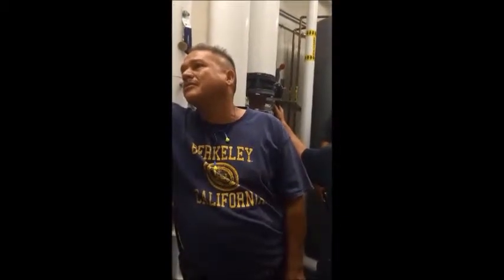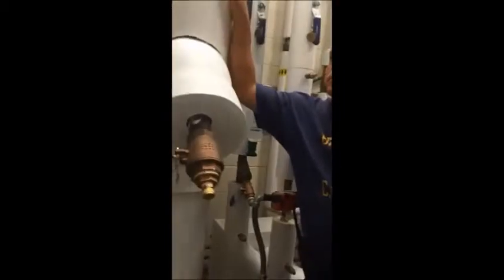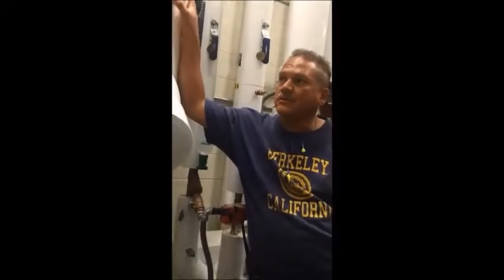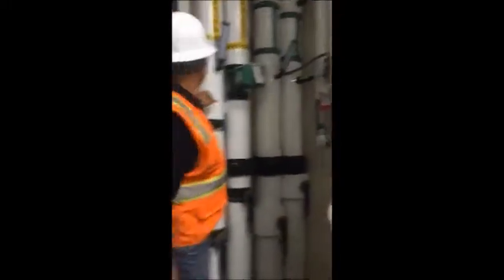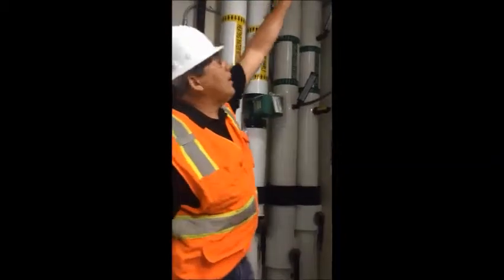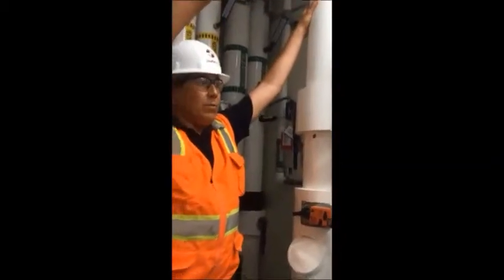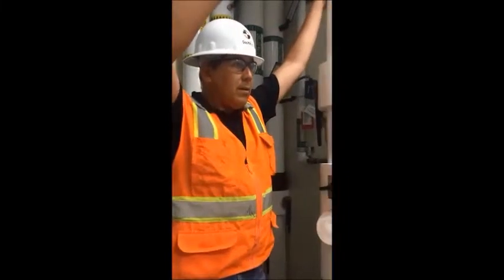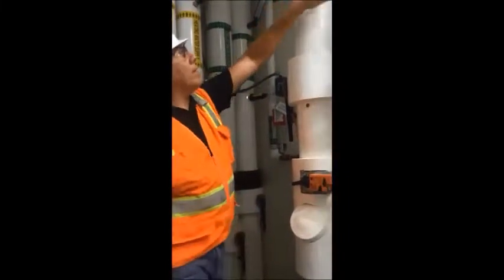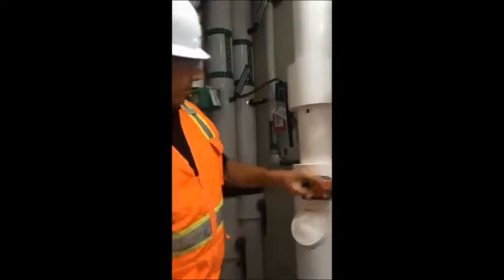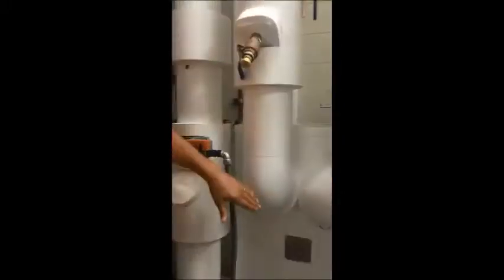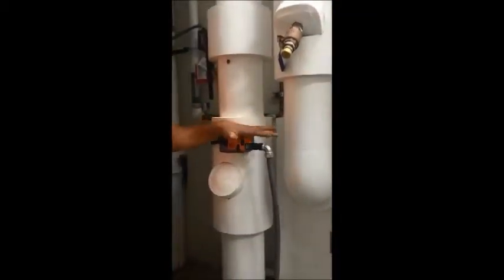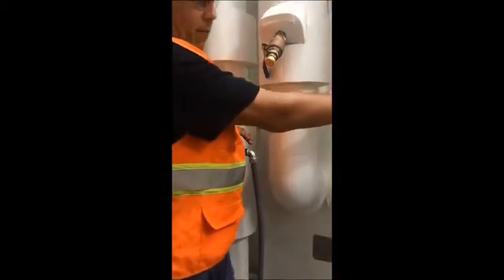So which one is feeding the chill beams? Okay, so these 2 pumps are actually feeding chill beams. Ultimately, when the chill water supply goes out, it feeds air handlers 1, 2, and 3 directly, straight from the line. Correct. And then this water right here off the chill water supply comes to the control valves on the return side. So this is the primary side of the heat exchanger. This is the secondary side. This side is 44. That's why I say if this control valve fails, it's going to make this side 44, which just runs at 58.